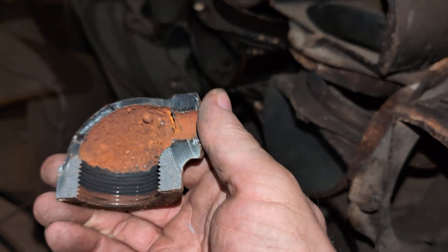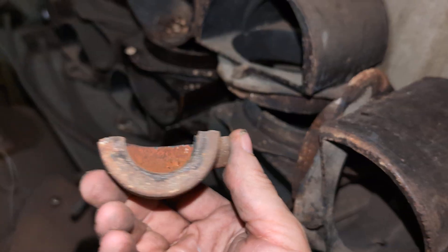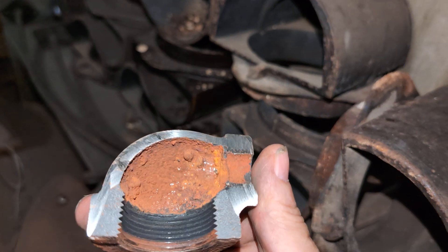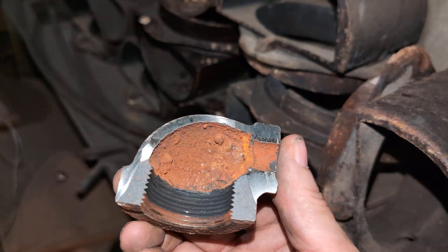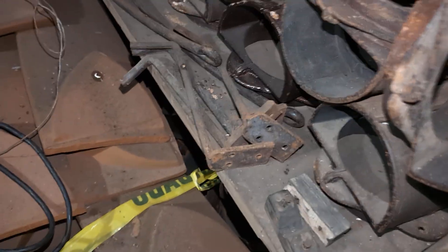When I chopped off the reducing 90s — a lot of them were lying on their side — literally about half the pipe was full of water and sludge when I cut it open. You can see where I ground it with the abrasive cut-off and then cracked it off with wedges. And these are the air vents above, under the seating.